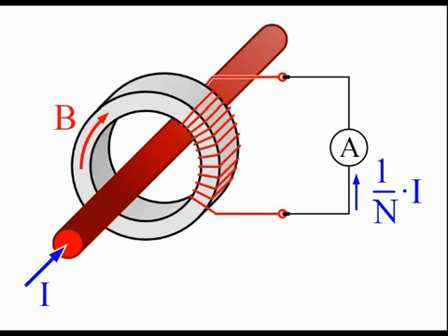industry. Like any transformer, a current transformer has a primary winding, a core and a secondary winding, although some transformers, including current transformers, use an air core. In principle, the only difference between a current transformer and a voltage transformer, normal type, is that the former is fed with a constant current while the latter is fed with a constant voltage, where constant has the strict circuit theory meaning. The alternating current in the primary produces an alternating magnetic field in the core, which then induces an alternating current in the secondary.